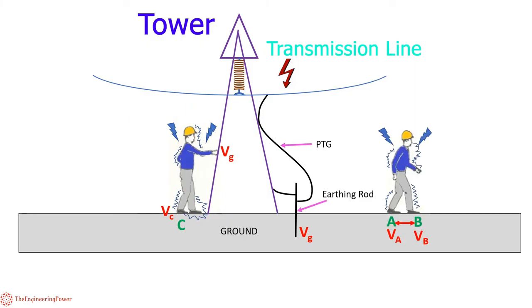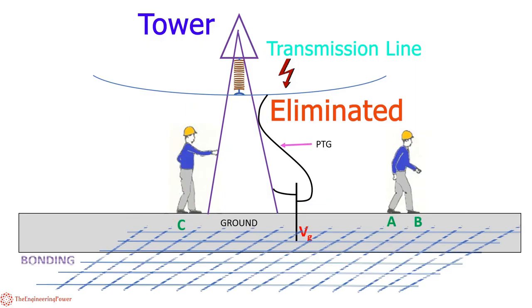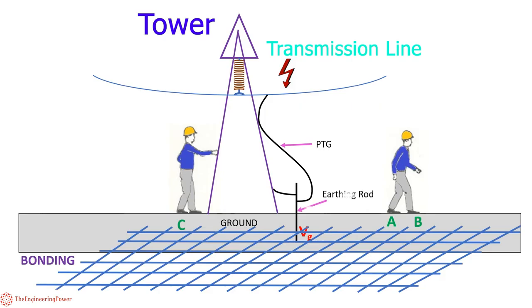Now both of these potentials and electric hazards can be eliminated using bonding. By connecting the earthing rod to the mat or earth mesh provided in the work area, all the earth mesh will be at the same potential, i.e. ground potential VG, thereby eliminating any chance of electric shock.